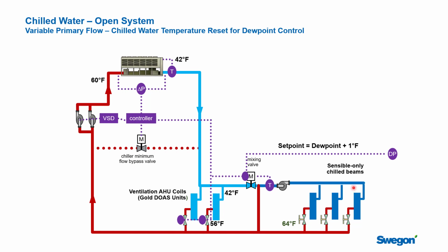A different sequence would be to say, okay, something is amiss. Something is not happening the way we expect it to. We can see the start of high dew point in the space through dew point sensors. And this time, what we're going to do is, now that we know the dew point has climbed above 57 degrees, it's 58 or 59, we measure that, and we reset this chilled water temperature to be 1 degree above whatever we see in the space.